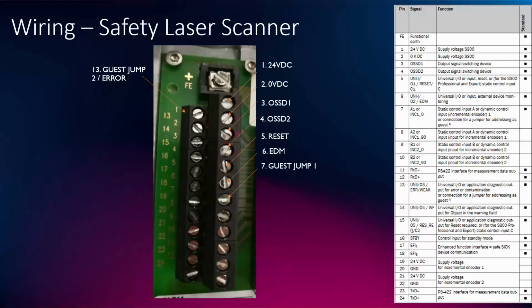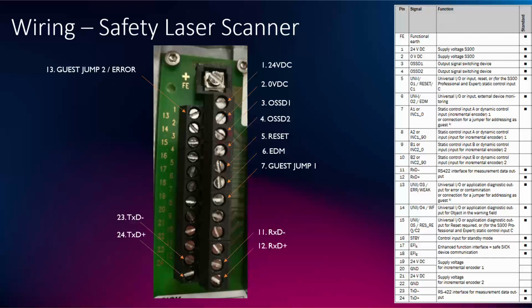Pins number 7 and 13 may be wired together if the device is to be used in a multiple safety laser scanner system as a secondary device or a guest device. The pin number 13 doubles as an error signal output, which can be used to signal a device error or contamination in the device's viewfinder. Pins number 11, 12, 23 and 24 can be used to wire an RS422 interface. This interface can be used for measurement data output.